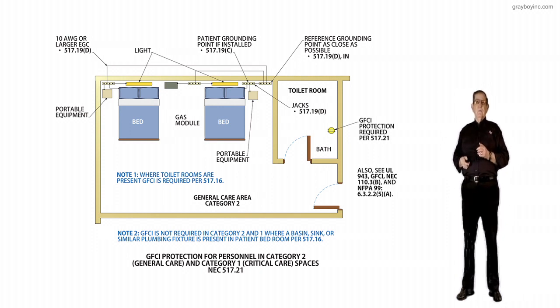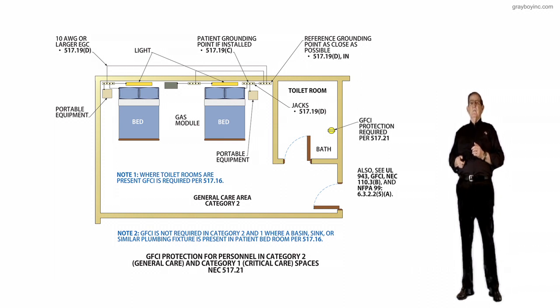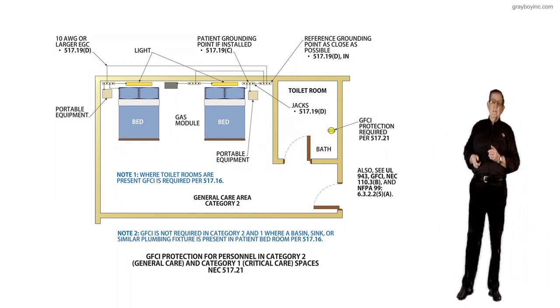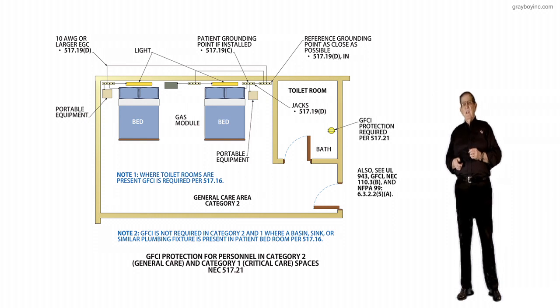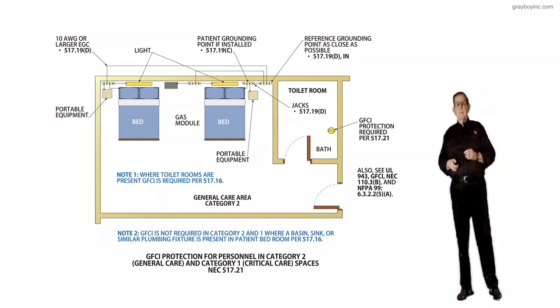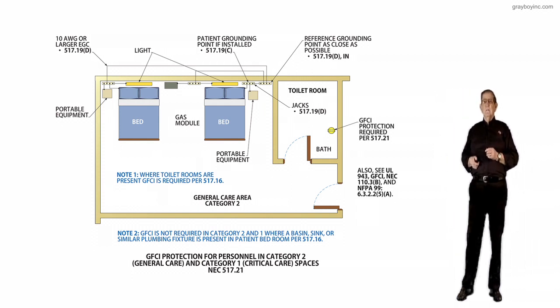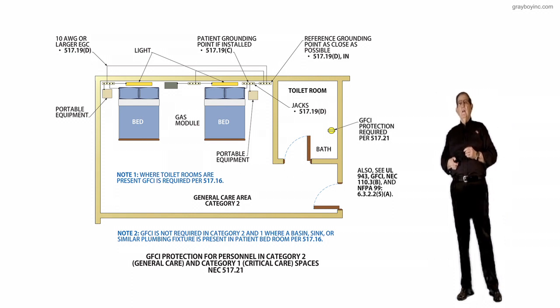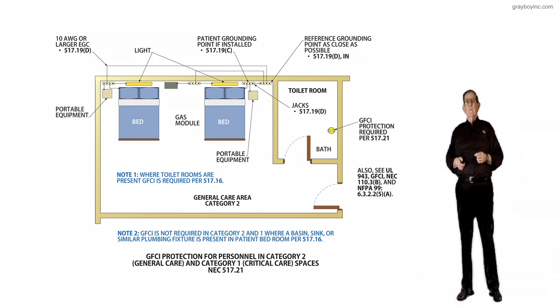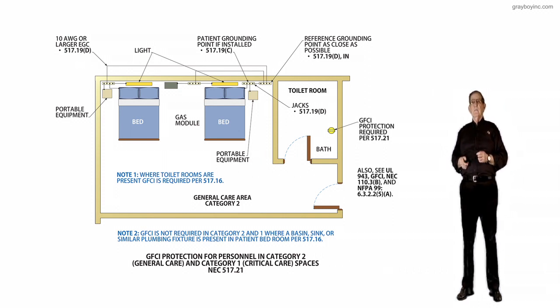If you are reviewing these GFCI protected receptacles and applying safety-related rules, then you look at 110.6A through D, and you find that about every month you have to test them for their reliability, that they're dependable, that people who use them are indeed still protected by GFCI systems. So we would make sure that we review that and look at it.